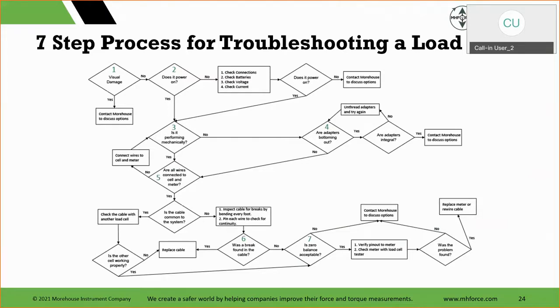Something we haven't discussed as much is another diagnostic or test. If you're troubleshooting and you have two cables, maybe you just swap cables. If one cable works and the other one doesn't, then you know there's a problem with the cable. I still like the bend test. That's just another shortcut if the cable is bound to the system. You can check with another cable and another load cell. So, it's like A/B testing, right?